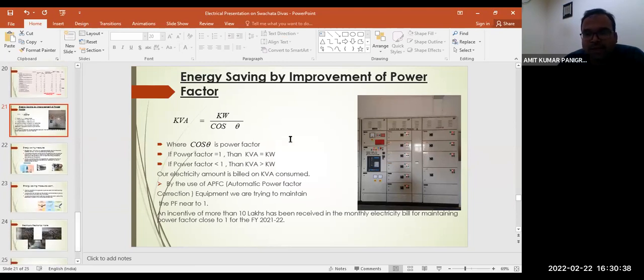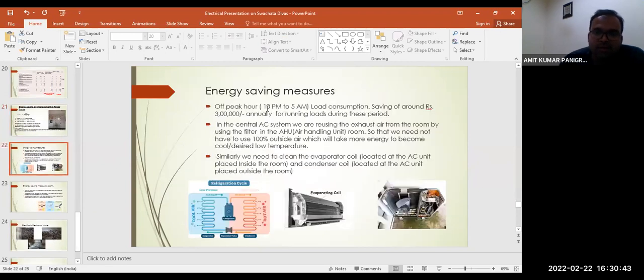So this is one type of energy saving and also cost saving. And then we will see the general ways of energy saving measures. How we can save the energy, or inside NISER, how we are saving energy. The main one is the off-peak hour load. As we have previously discussed, if we run most of the loads during the night time, 10 p.m. to 5 a.m., then the off-peak hour loads unit consumption will be more, and we are getting incentive for that.